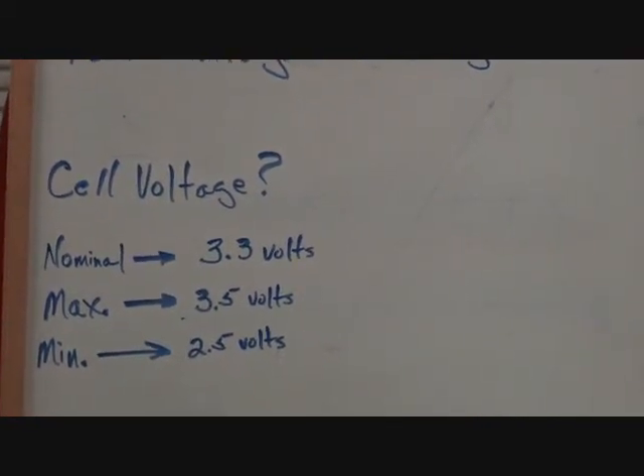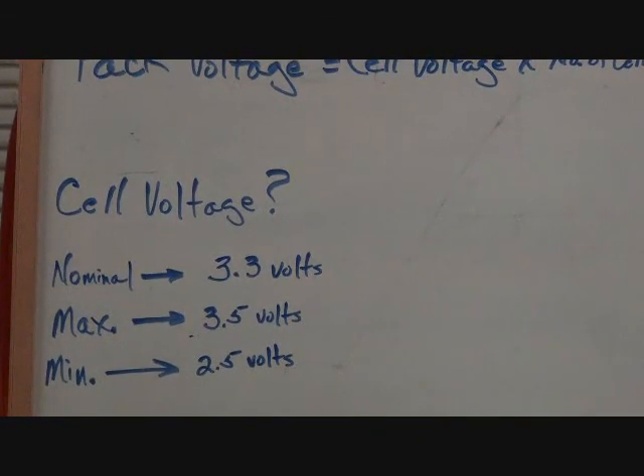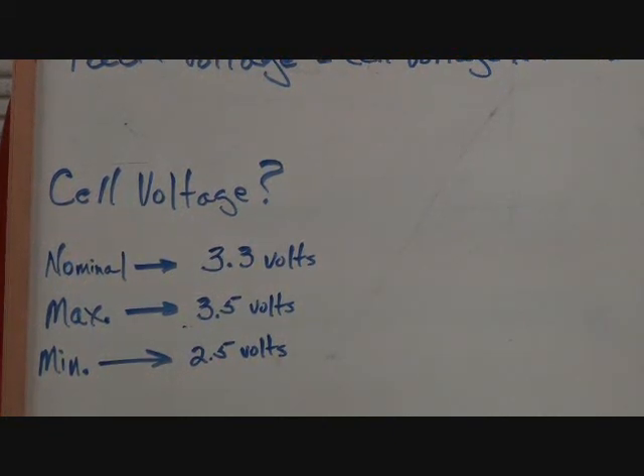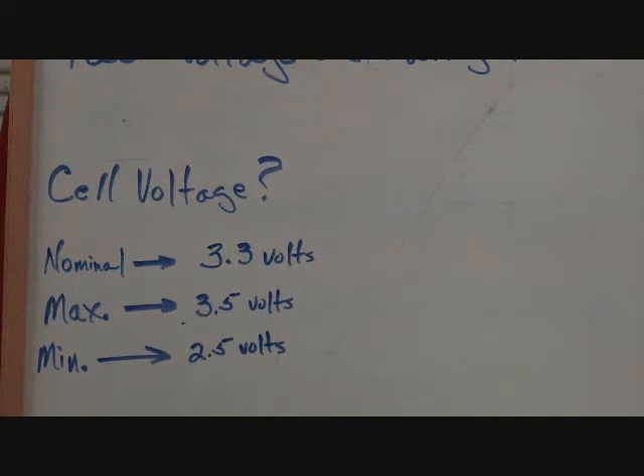The cell voltage of a lithium iron phosphate cell, nominally, is 3.3 volts. But the maximum that we charge them to is 3.5 volts. So when it is first charged, those cells will each be 3.5 volts. And then there's a minimum that we will never discharge beyond. Matter of fact, we don't take ours down this low even, but the maximum that you can discharge it to is 2.5 volts.